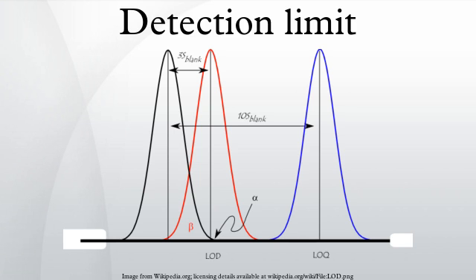The experiment is repeated ten times. The three sigma of the recorded absorbance signal can be considered as the detection limit for the specific element under the experimental conditions used for the wavelength and instrument.